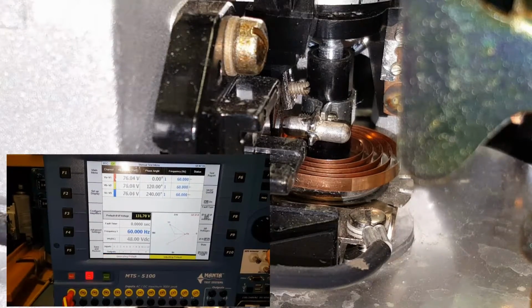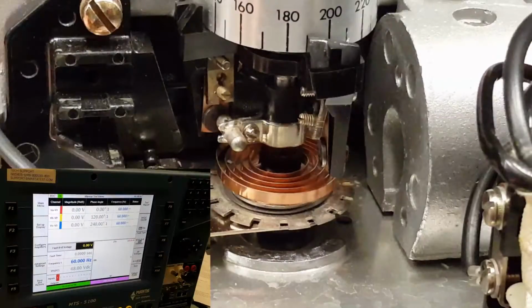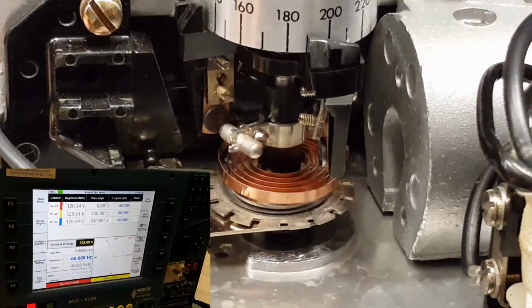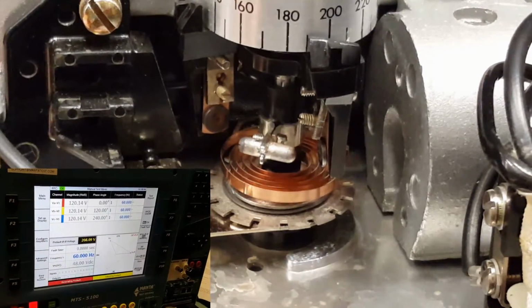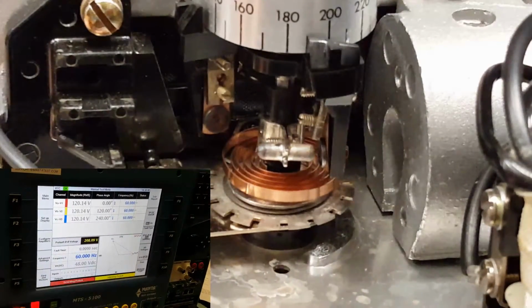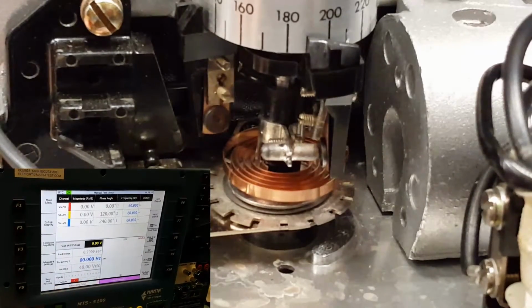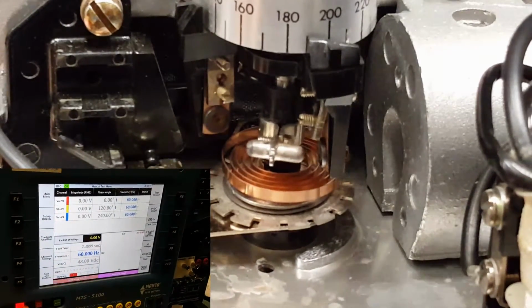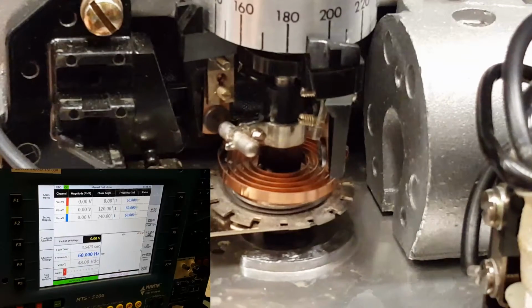For the undervoltage timing test, we're looking at 3.7 seconds nominal, plus or minus 4%. What we're going to do, we're going to ramp the voltage up until it makes contact with the high voltage contact. We're going to drop all 3 phases to 0, and we're going to record the time that it takes to make up the low voltage contact.